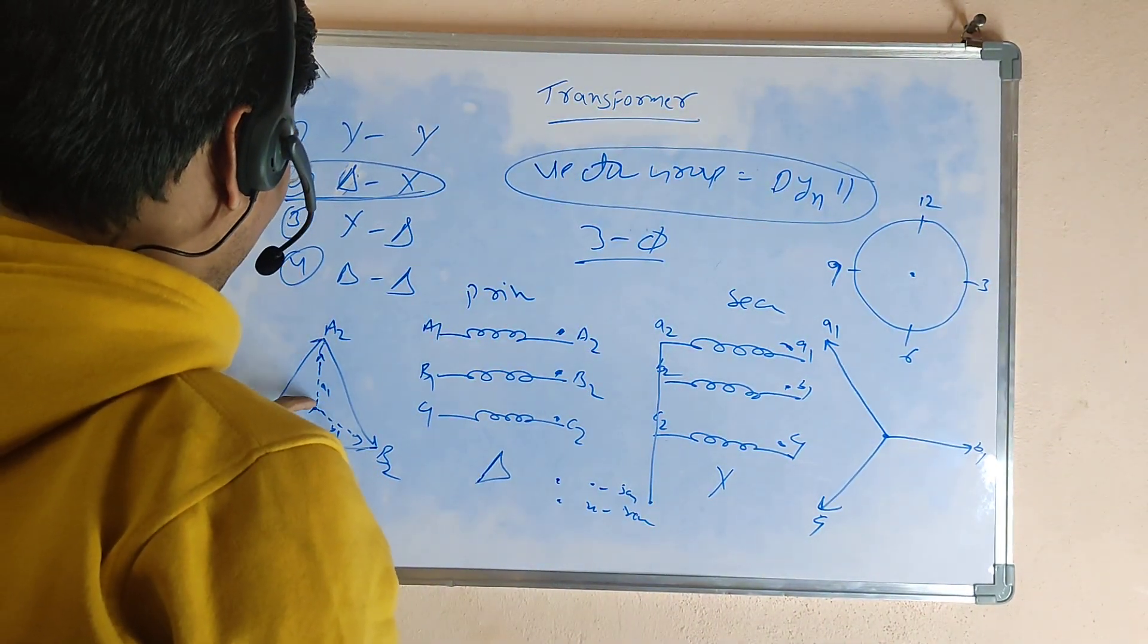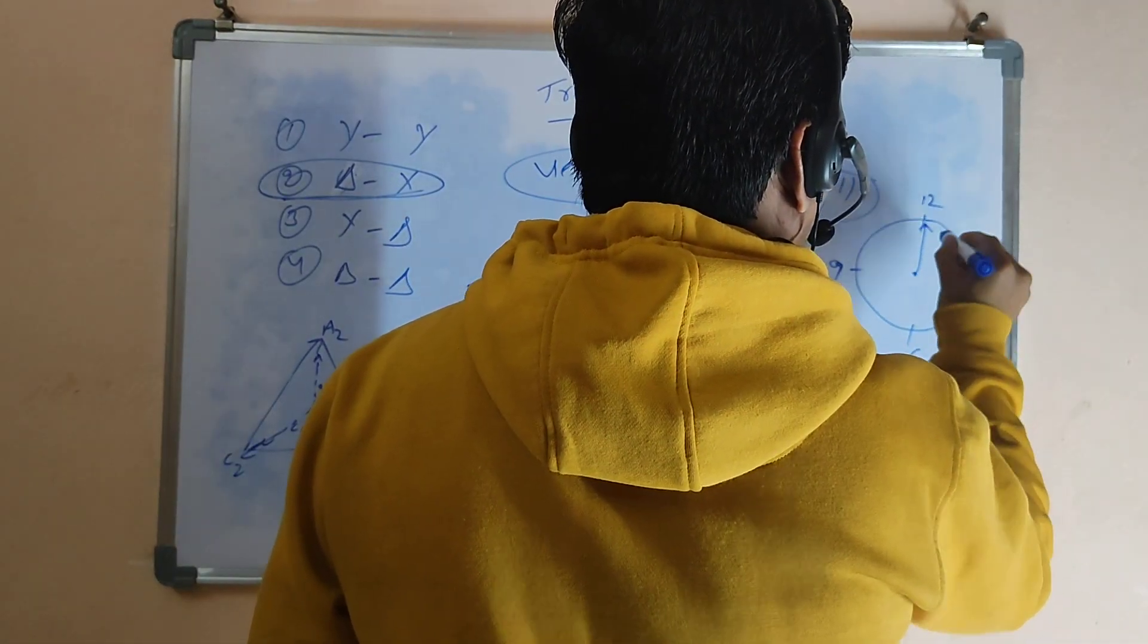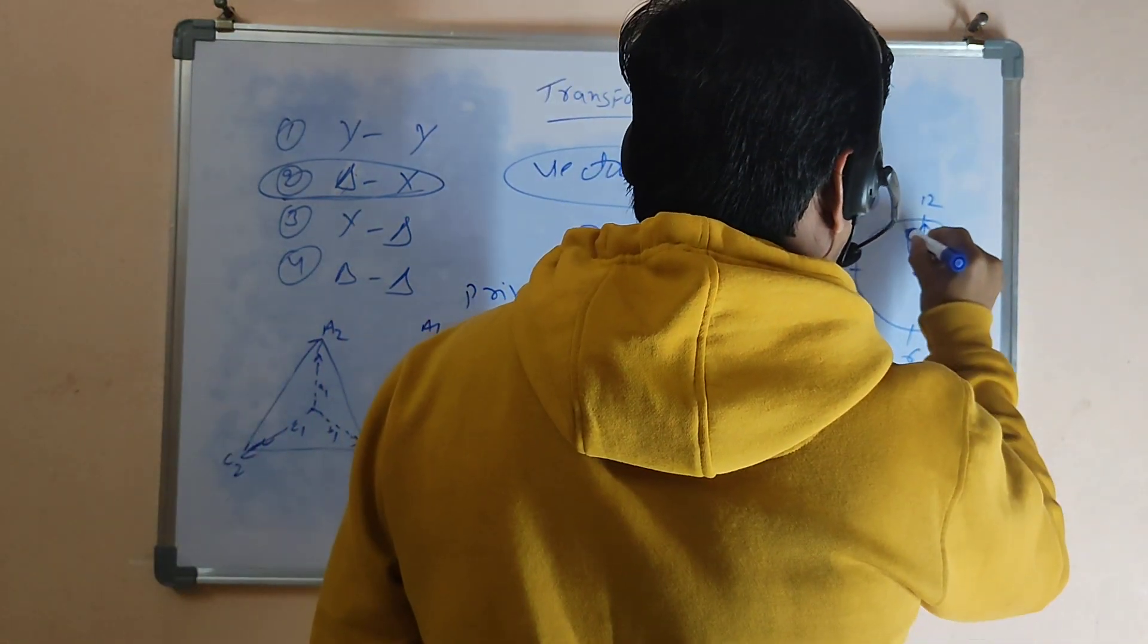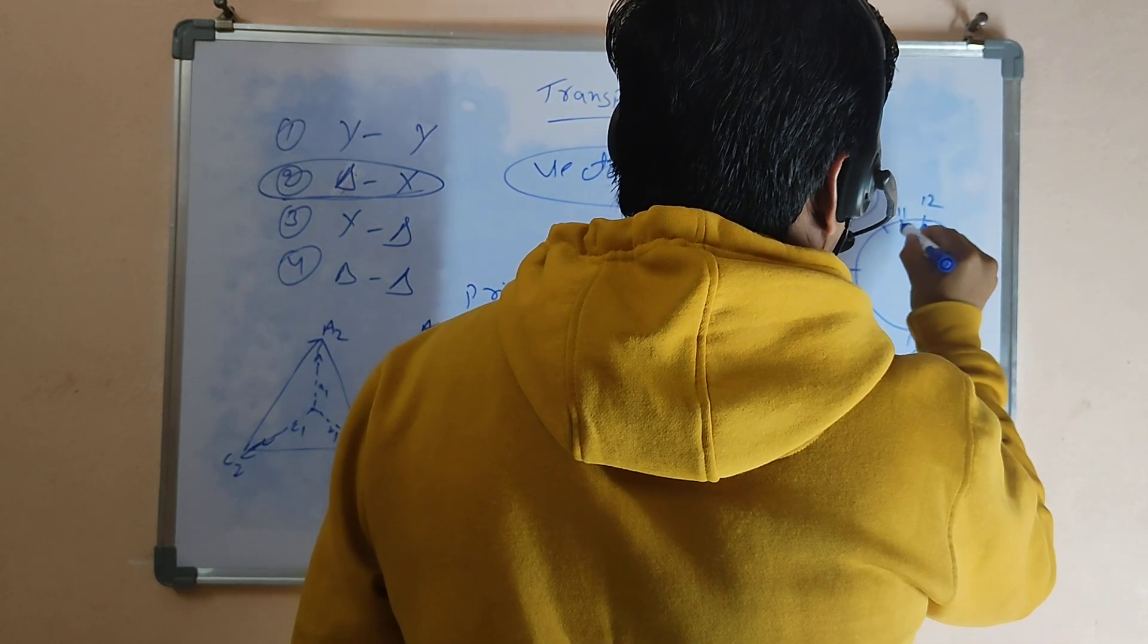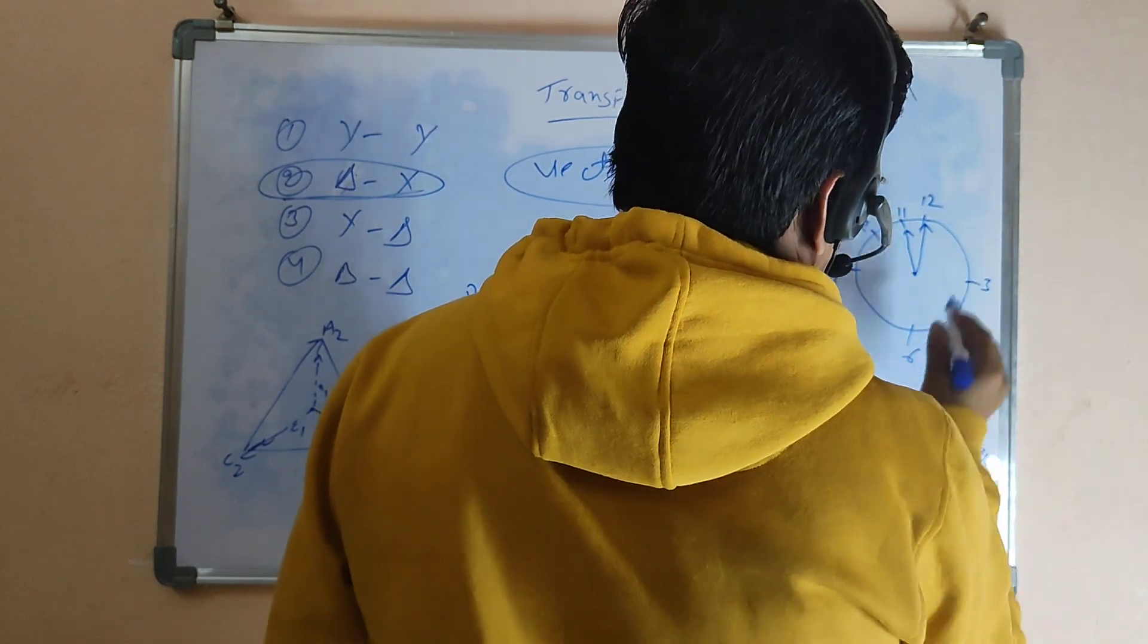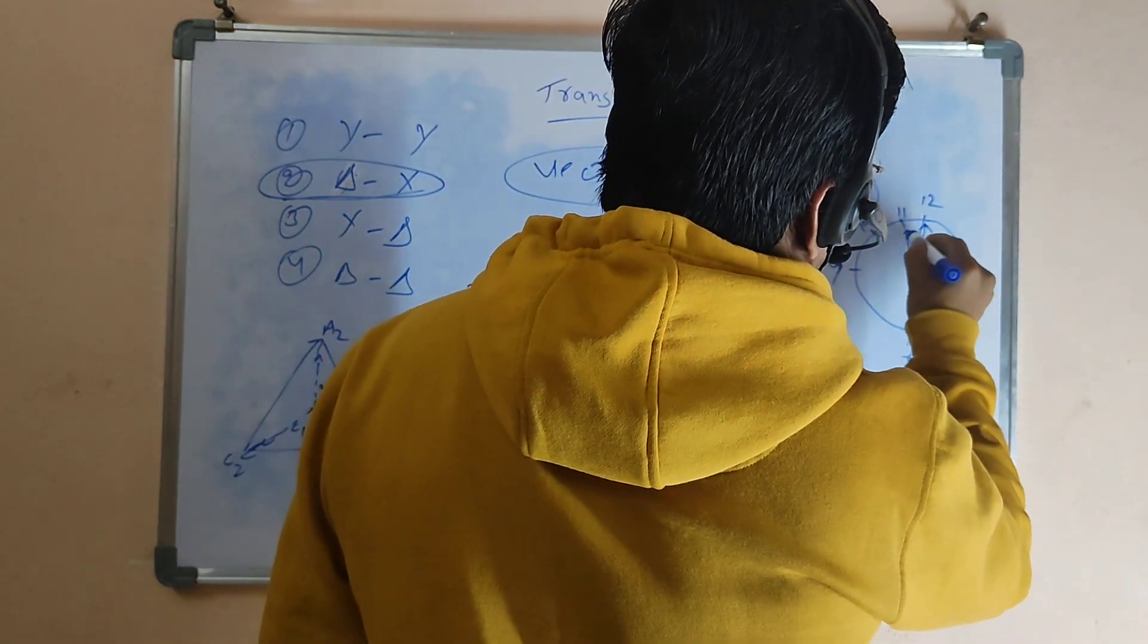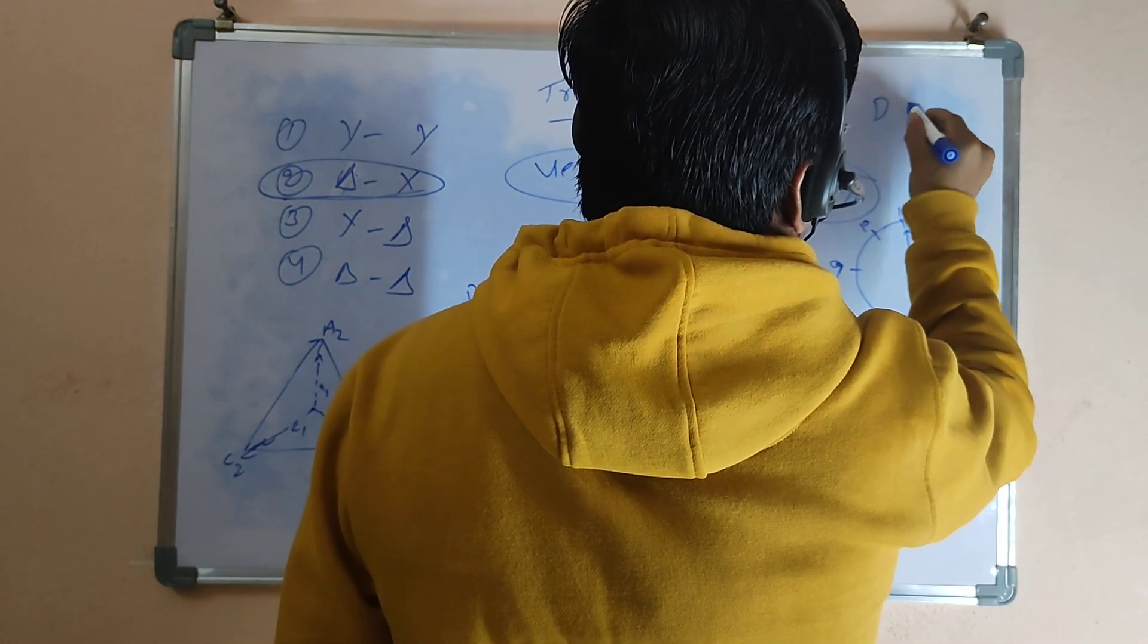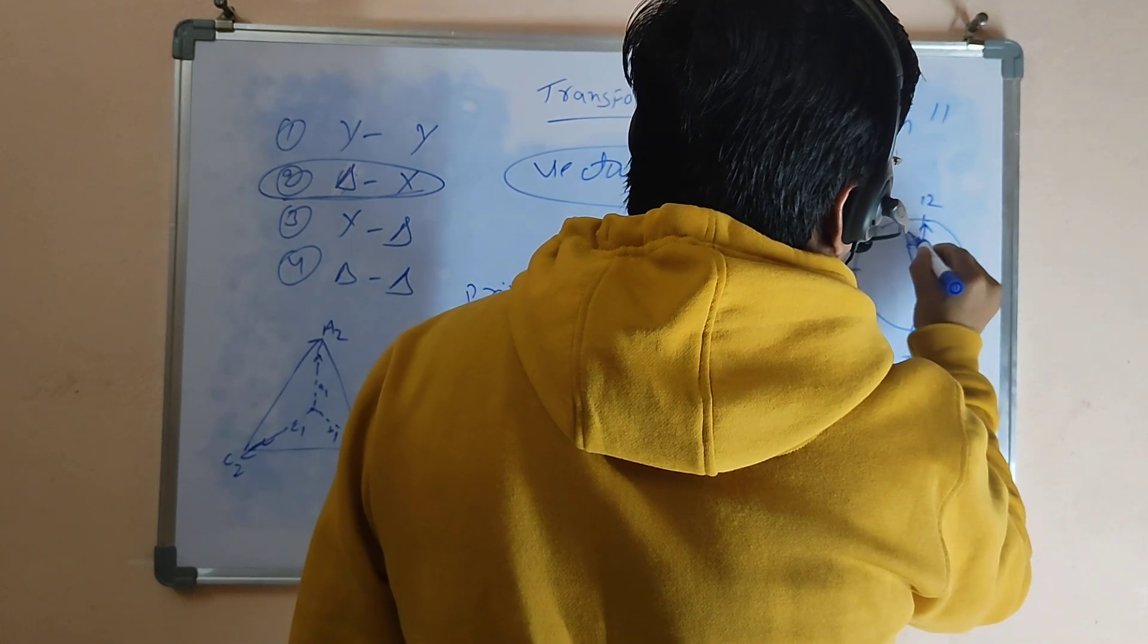Now we draw: this is the A1. This is 11 o'clock. The time is 11 o'clock. That is nothing but D, Y, N, 11 o'clock. That means the angle between this and this is 30 degrees.